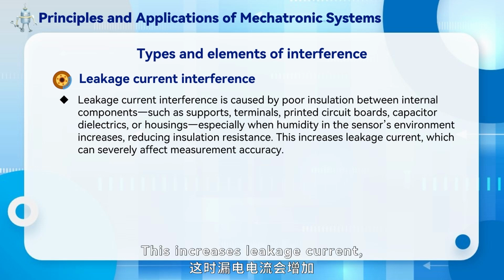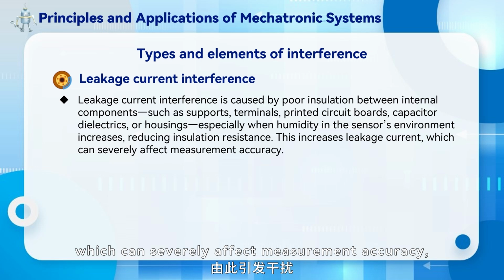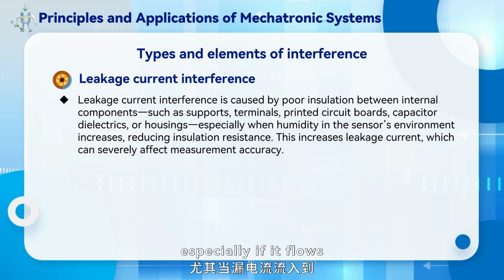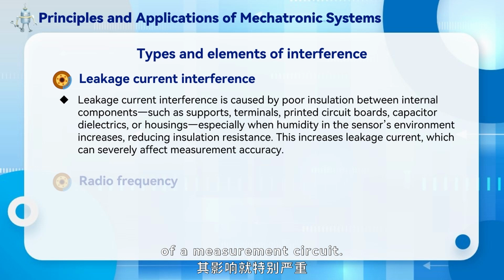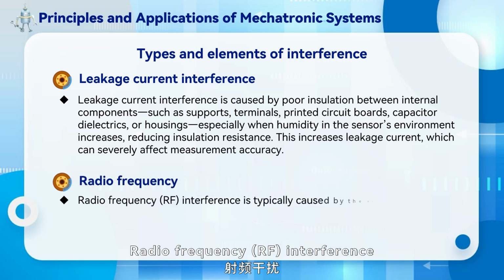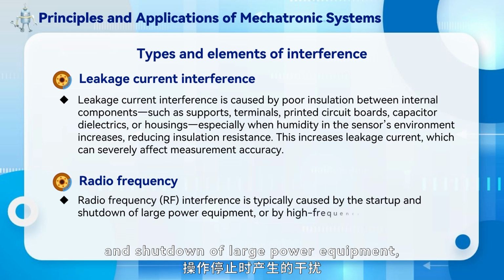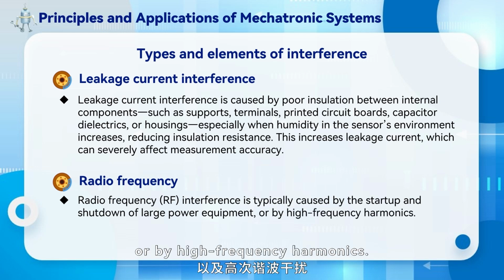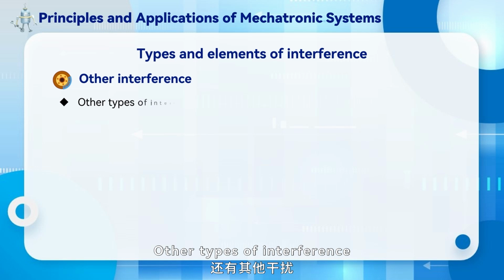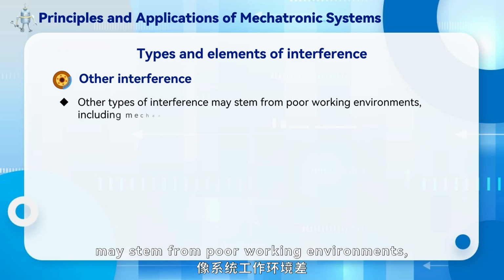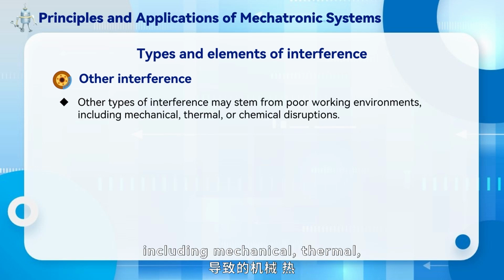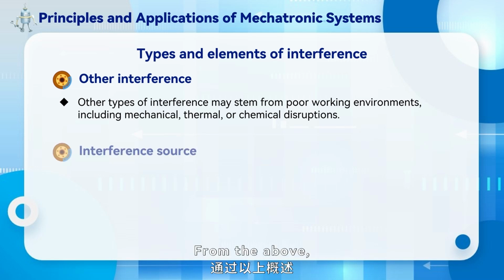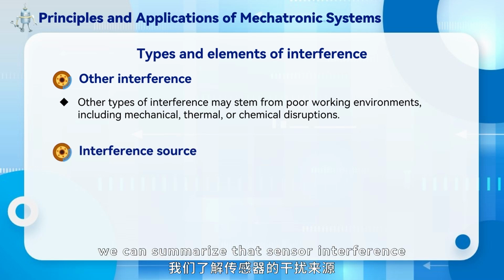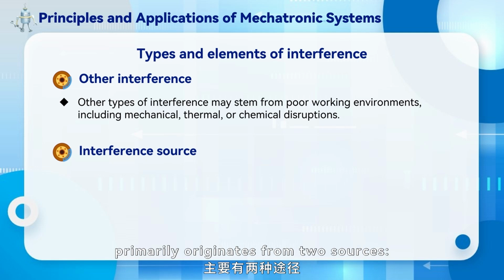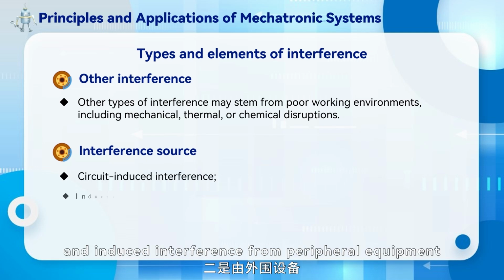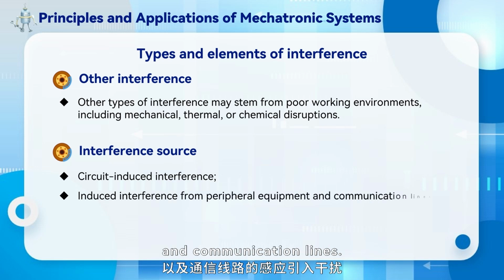This increases leakage current, which can severely affect measurement accuracy, especially if it flows into the input stage of a measurement circuit. Radio frequency, RF, interference is typically caused by the startup and shutdown of large power equipment, or by high-frequency harmonics. Other types of interference may stem from poor working environments, including mechanical, thermal, or chemical disruptions. From the above, we can summarize that sensor interference primarily originates from two sources: circuit-induced interference, and induced interference from peripheral equipment and communication lines.